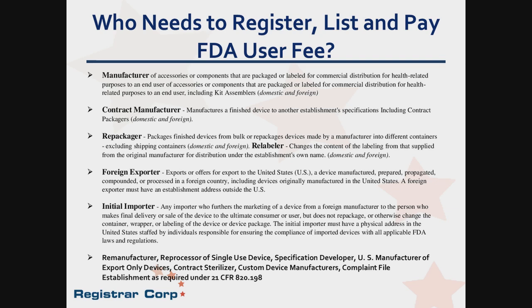Functions that would require registration would be a remanufacturer of medical devices. And maybe I can add here, remanufacturing means that you are really changing a device. You are not refurbishing a device. Refurbishing means that you just clean a device, you recalibrate a device, and you are selling it. Remanufacturing means that you might add additional functions. You really change the specifications from the original manufacturer. So if you are doing that, that would be called remanufacturing and would also require registration and listing.